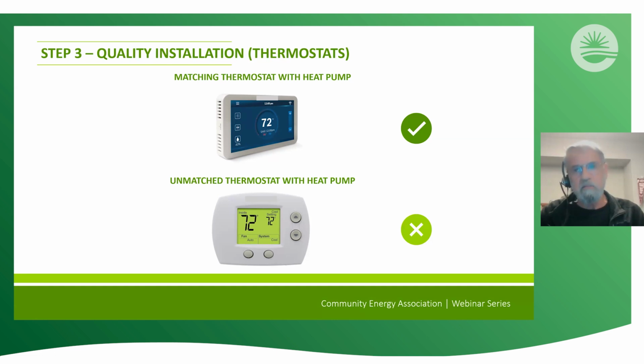And then there's the other category, which is non-communicating, which means that your thermostat doesn't need to match the equipment. It's better if it does, but if it doesn't, that's okay, because now what you've done is you've reduced your equipment to on and off. You've taken out that data sharing between the operation of the equipment and the ability to use that data with algorithms to optimize its performance. So ideally, you want a matching thermostat. Doesn't mean you have to have it. That's just ideal. The ideal next step in having quality installation.